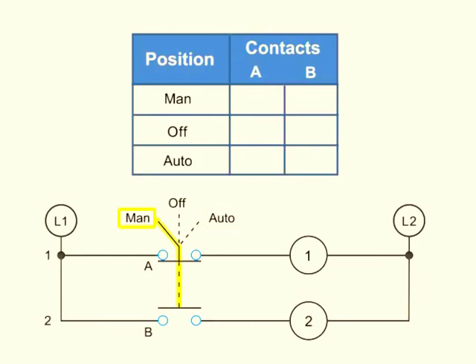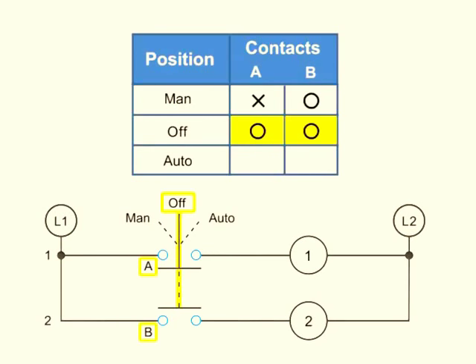Thus, in the MAN position, A is X or closed and B is O or open. At the OFF position, both A and B are O or open. With the selector switch set to AUTO, contact A is O or open and B is X or closed.